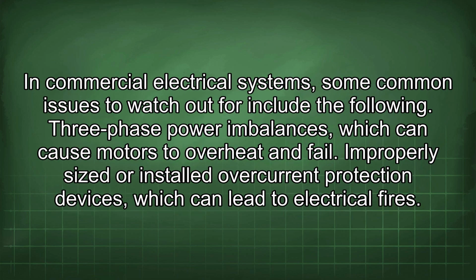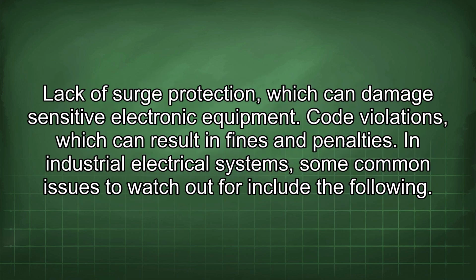In commercial electrical systems, some common issues to watch out for include the following. Three-phase power imbalances, which can cause motors to overheat and fail. Improperly sized or installed overcurrent protection devices, which can lead to electrical fires. Lack of surge protection, which can damage sensitive electronic equipment. Code violations, which can result in fines and penalties.